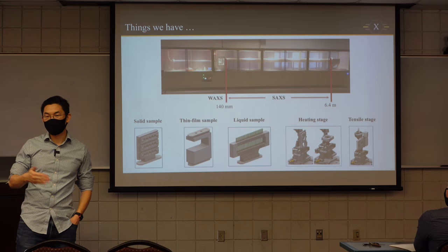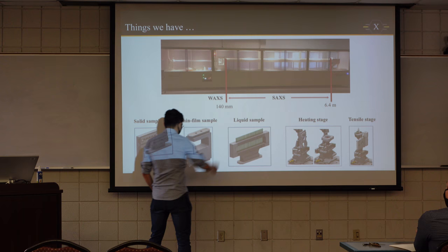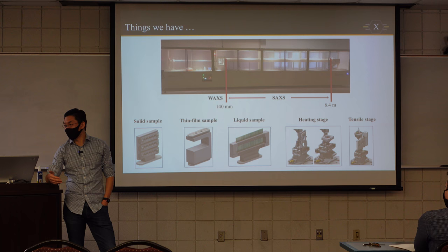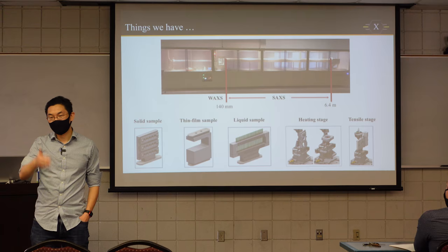The other option people use is quartz slides, and we will talk a little bit about liquid samples here. There are other materials for some applications, for example, if you really worry about Kapton scattering or absorption. The other option is a silicon nitride window. It's a very thin layer of inorganic material that can go as thin as 100 nanometers. It's going to be brittle, but it serves the purpose of giving an amorphous, weak background.